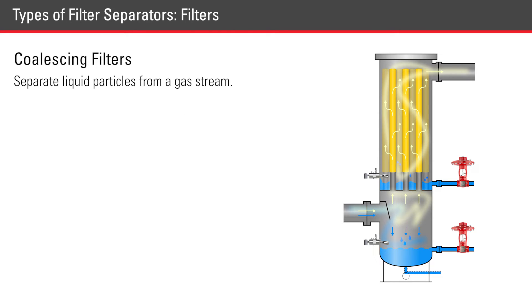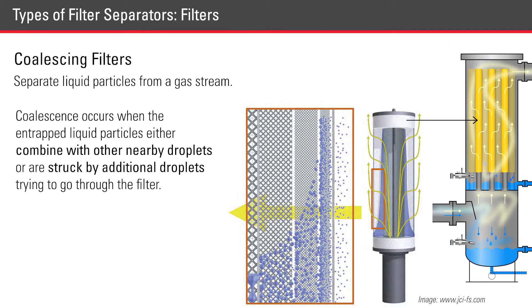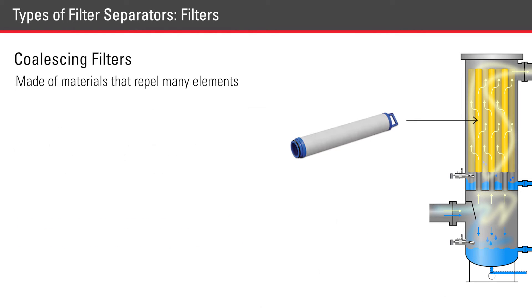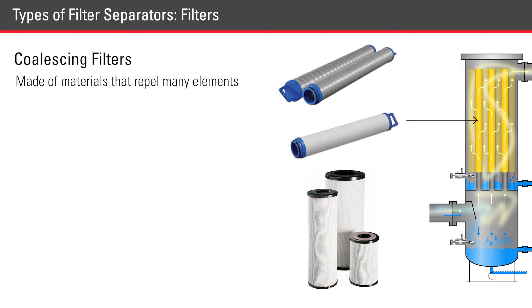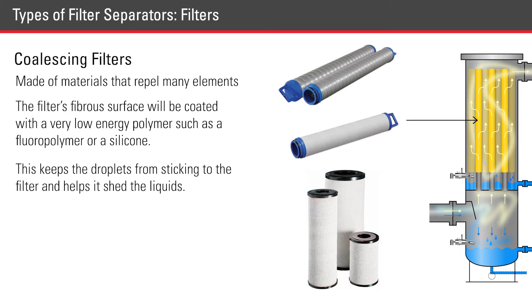Coalescing filters separate liquid particles from the gas stream. Coalescing occurs when the entrapped liquid particles either combine with other nearby droplets or are struck by additional droplets trying to go through the filter. Coalescing filters are made of materials that repel many elements. The filter's fibrous surface will be coated with a very low-energy polymer such as fluoropolymer or silicone, which keeps the droplets from sticking to the filter and helps it shed the liquids.